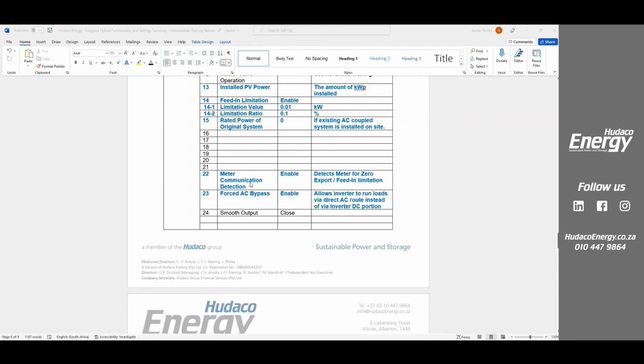Meter communication detection. Enable this, please. This is what allows the meter to detect for that feed-in limitation. If you disable this, okay, it will stop exporting through your grid port altogether. It will still operate as a backup system only, but it will stop sending any power back through to feed your non-essential loads. Okay, so as long as your meter's there, enable it and it'll run your non-essential loads.